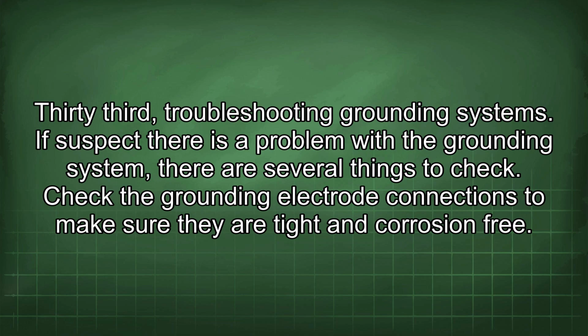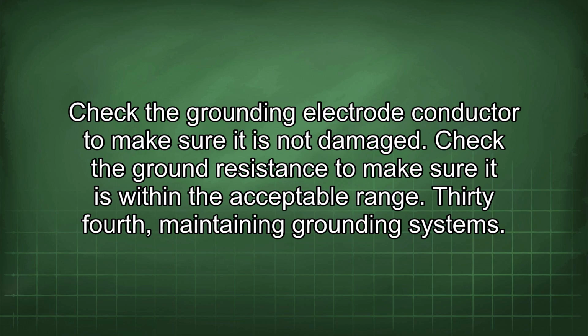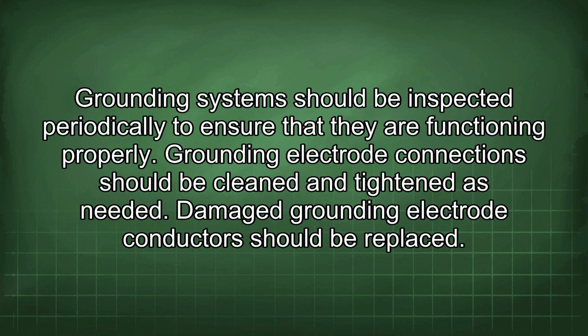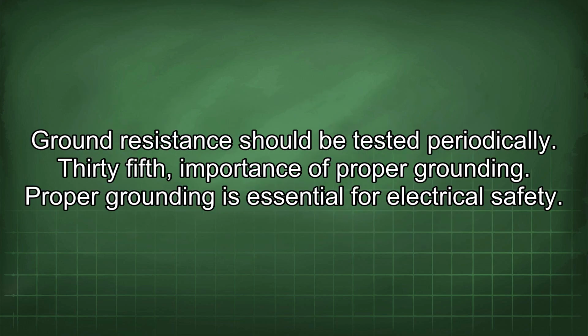33rd, troubleshooting grounding systems. If you suspect there is a problem with the grounding system, there are several things to check. Check the grounding electrode connections to make sure they are tight and corrosion-free. Check the grounding electrode conductor to make sure it is not damaged. Check the ground resistance to make sure it is within the acceptable range. 34th, maintaining grounding systems. Grounding systems should be inspected periodically to ensure that they are functioning properly. Grounding electrode connections should be cleaned and tightened as needed. Damaged grounding electrode conductors should be replaced. Ground resistance should be tested periodically.